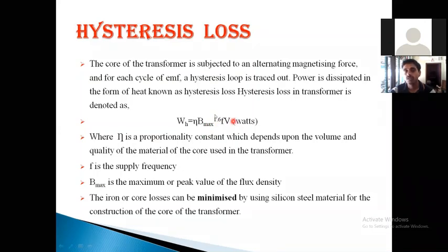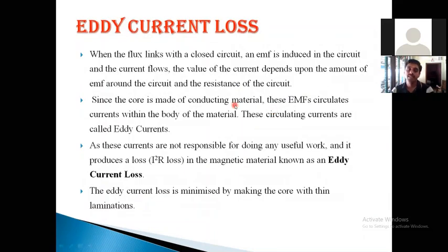This we have seen in the motors also. What is F? What is V? F is the frequency of magnetic reversals, and V is the volume of the core. This can be minimized by using silicon steel material; with the proper selection of the material, hysteresis loss can be reduced. Coming to the eddy current loss, as I said, when the flux varies, EMF is induced in the circuit and current flows. The value of the current depends upon the amount of EMF induced. It will produce losses within the core. They are called eddy current loss. These eddy current losses can be reduced by using laminations.